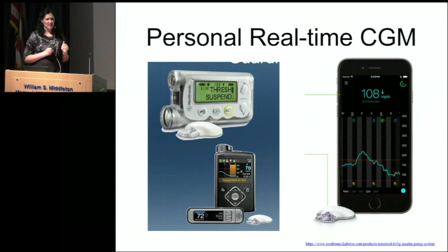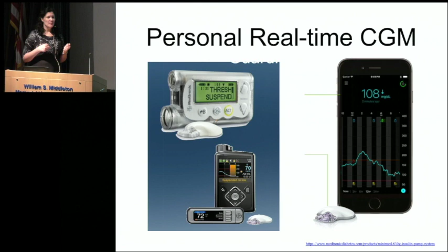The other company producing real-time CGMs is Medtronic. These were the first to be incorporated with an insulin pump. The two available currently are the Medtronic Enlite, a sensor with MiniLink Guardian that can be used with the Medtronic 530 and 630 insulin pumps. These sensors can be worn up to 6 days, and they do require calibration, unlike the other devices.